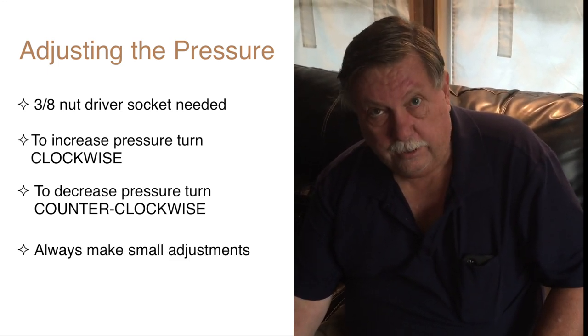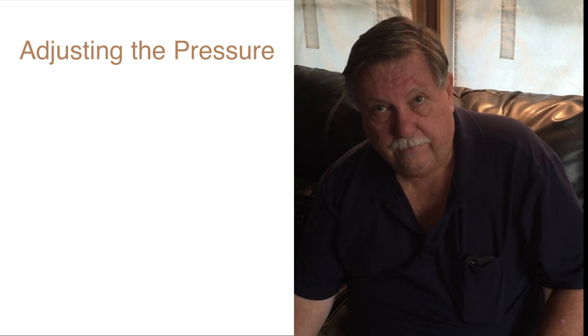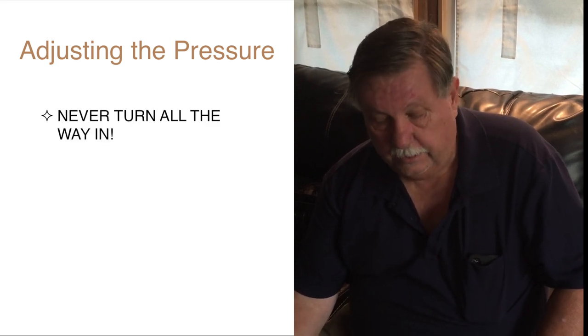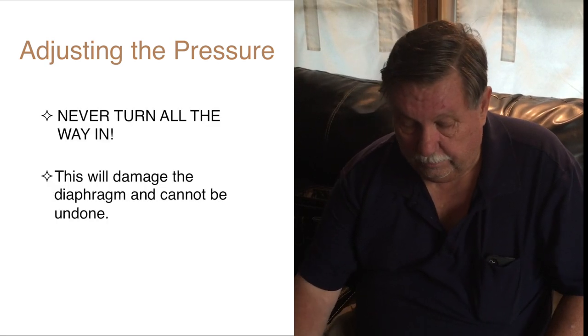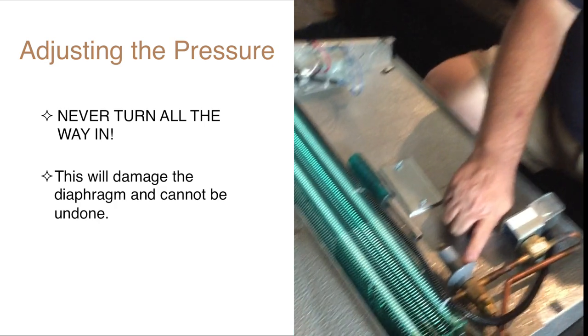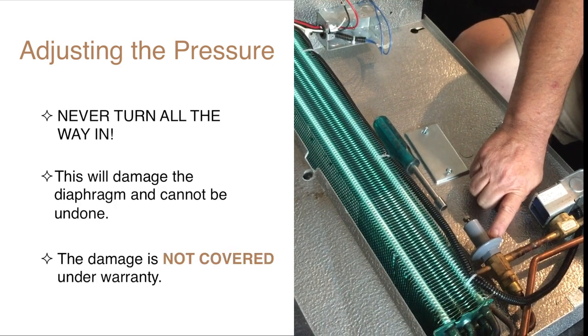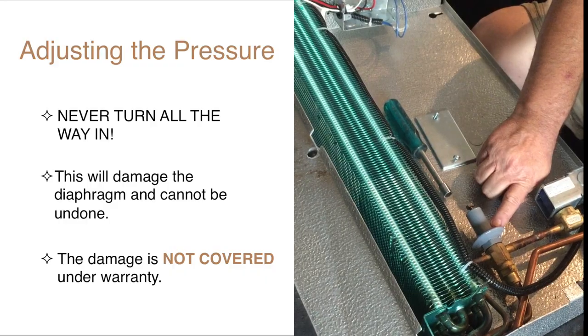Remember, make small adjustments and never go all the way in with the adjustment. If you go too far in, you can damage the bellows and then the expansion valve will no longer adjust.